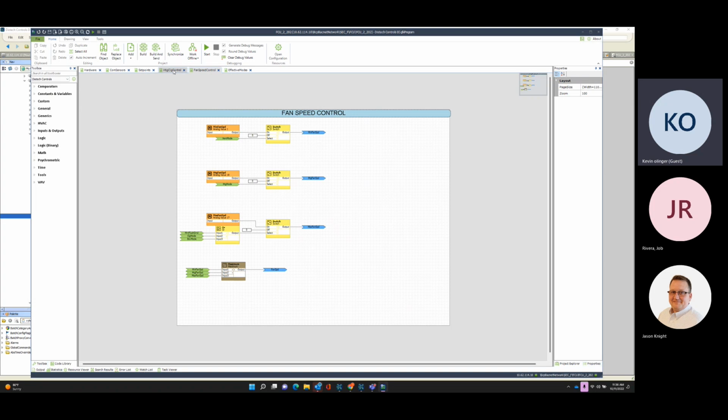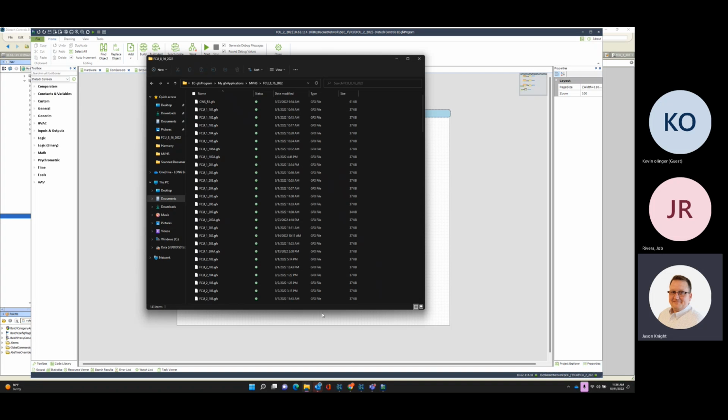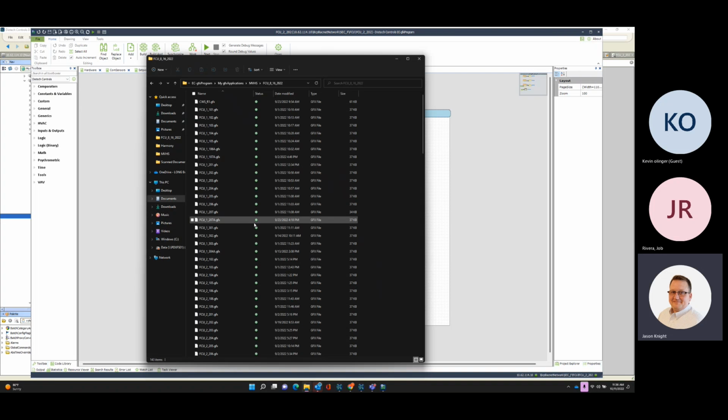And is it fair to say that right now, because these are, I'm assuming, from the engineering team, that everywhere in the building they are consistent, whatever you said, 32% on all of them? None of them have been tweaked like you're showing for individual reasons. Yeah, everything is set right now per what the design standard was. Excellent.